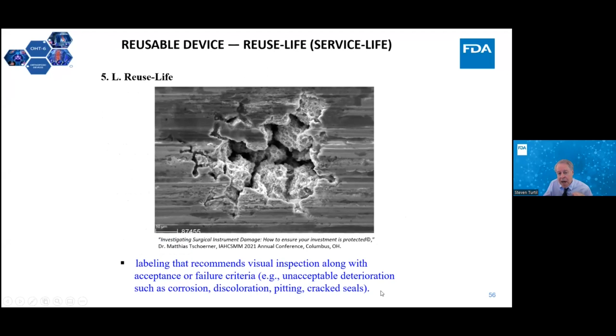So we want to see in the labeling some specification that addresses one or all of these. Not all, I'm sorry, I take that back. At least one of these that addresses everything, and maybe a combination of them. But what I see, I'm just giving you my examples working in orthopedic devices. They're, you know, a lot of metallic devices. We very often see: do a visual inspection, not separate from the cleaning inspection, but a visual inspection that identifies corrosion, discoloration, pitting, cracked seals. And when you see that, appropriately dispose of the device.